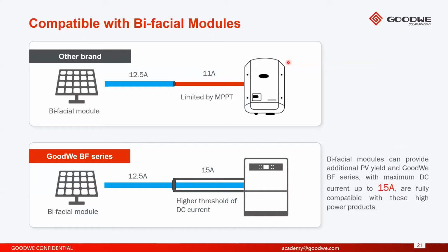Our inverters are also compatible with bifacial modules, which are becoming the standard now in today's PV landscape, not only in the commercial, but also in the residential sector. By virtue of this, inverter manufacturers have also had to increase the maximum input current of the inverters, because bifacial modules have much higher short circuit current, which means that the short circuit input current of the inverter has to be increased over time. So our new inverters that we're releasing over the last year and this year and next year will accommodate the higher threshold of DC current delivered from the PV panels.